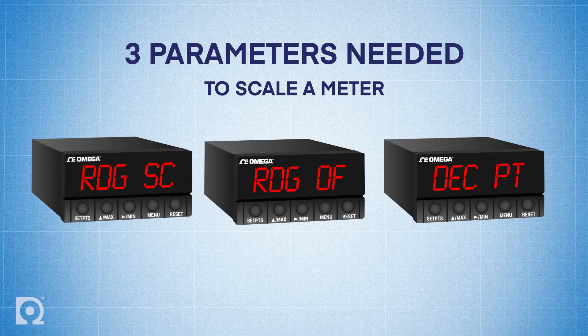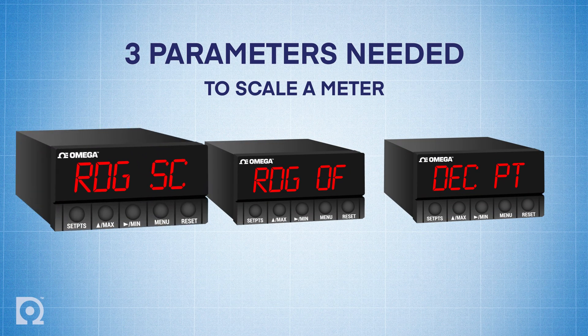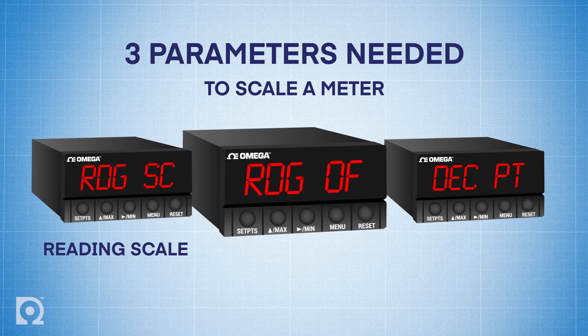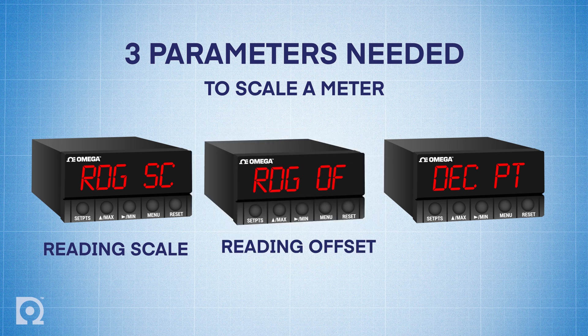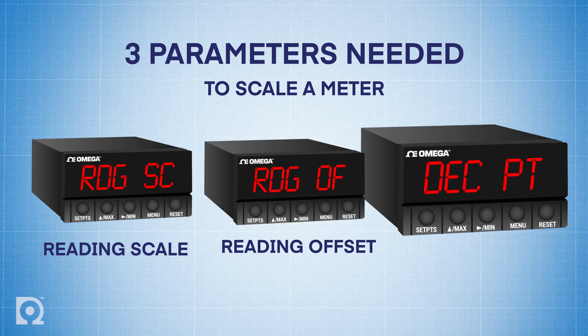To scale the meter, we only need three parameters: RDG-SC, which stands for reading scale, RDG-OF, which stands for reading offset, and DECPT, which stands for decimal point.